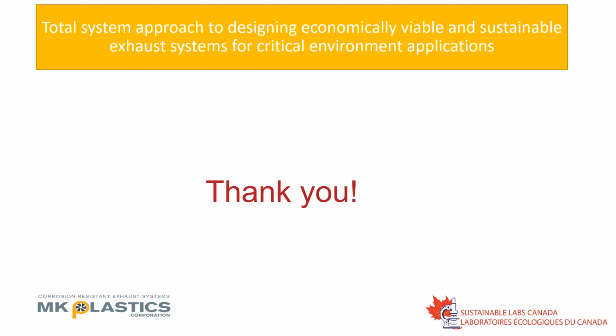So my experience with Aircuity is that it works very well with fans that have a turn down range somewhere in the 50% range, because that tends to be where you're at. I believe that Aircuity can turn down the air changes of a laboratory from anywhere from 8 to 12 down to something like 2 to 4. But there's probably people with more experience in Aircuity than me that can answer that question.